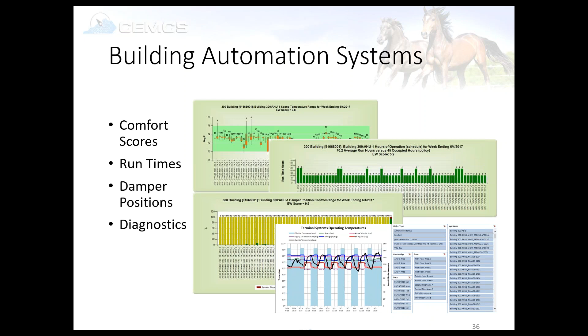This is the Cabinet for Human Resources building. It's a little over 300,000 square feet. We've been working to lower the pressure in the ductwork while maintaining proper air distribution. So you can see here we've been adjusting our static pressure reset from 4 inches water column to 2 inches water column, and that provides a dollar savings of up to $46,000 a year. That has kind of been raised back up, not all the way back to 4 inches all the time, but we're having some balancing issues that we're working through.